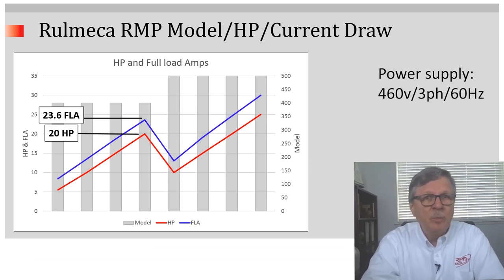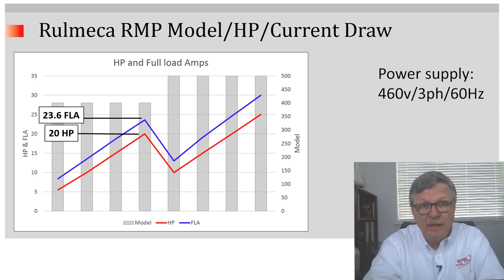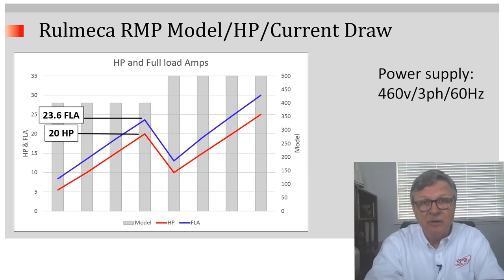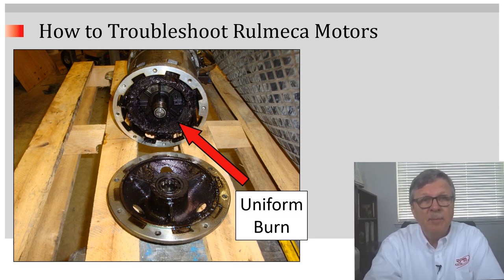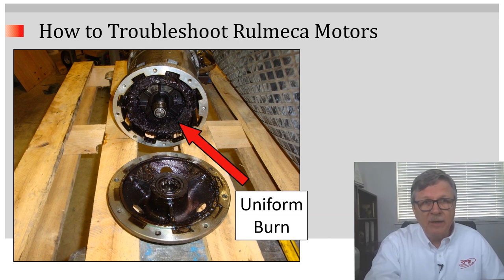Recall the graph shown previously: a 20 horsepower motor will draw 23.6 full load amps. If that motor is required to provide more than 20 horsepower, it will draw more than 23.6 amps — more like 30 or 35 amps. This is what a motor looks like when subjected to an overload condition. Notice that the stator is uniformly burned. So the question is: why was a 20 horsepower motor installed when 25 horsepower were required, and why was it allowed repeatedly to exceed full load amps?